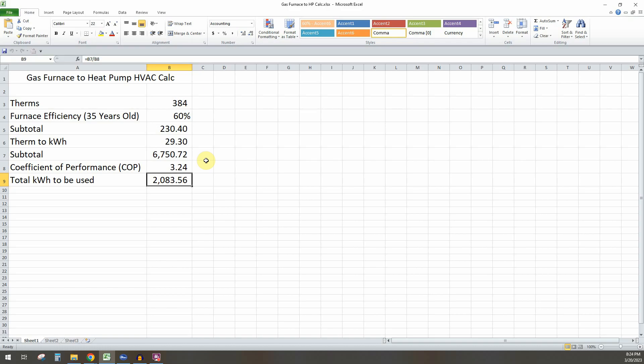And so that calculation is a lot more straightforward. That one is basically, you can pretty much almost take your AC condenser usage and just pile that straight into your budget there. However, you do need to look at the heat pump you're looking into and see how efficient it is. So for this M series Mitsubishi that we have, it's about two kilowatt hours an hour that it uses energy, which is much more efficient than the same type of three ton AC condenser.